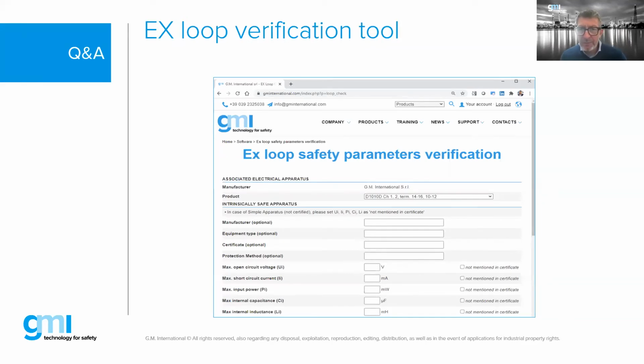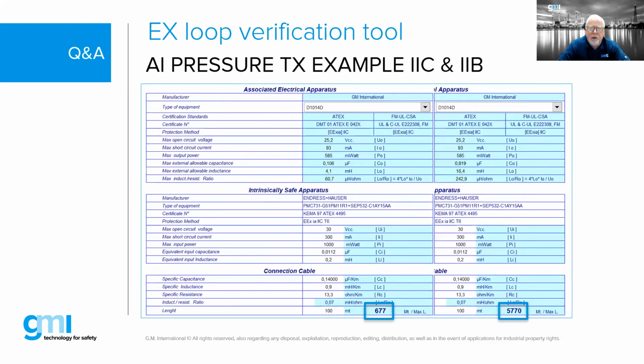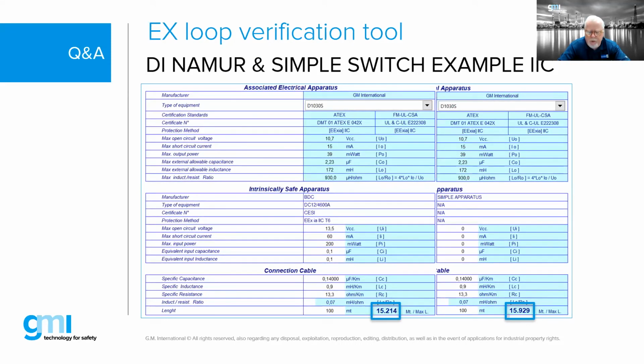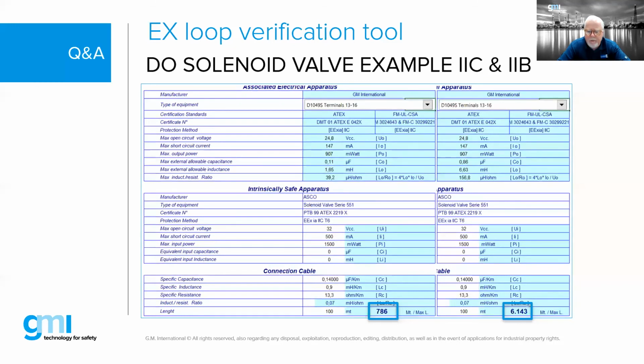Okay, we do have some more questions. As part of the regulation, do we need IS calculation and a DSD dossier for simple devices? Yes, you do. It is a requirement to create a DSD basically for all IS loops. So you are required to create this DSD, and that's based upon the IEC standard, with details in 60079-25. There are different formats, and the -25 standard shows how the format can be done, but yes, you should have calculations done.